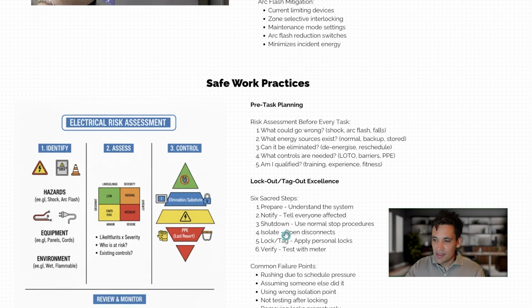Now, I mentioned this before, that lockout tagout is the principal way, when you have energy introduced into a system, that the people working on that system manage their own safety. It starts with pre-task planning, identifying what the work is, what systems they're going to be working on, what systems they're going to be working adjacent to, and how we isolate those. Typically on a project, you'll have an authorized isolation officer who's responsible for coordinating all of this. They work out where they are working and what they are going to be working near, they review the drawings, they plan the isolation, and they determine what systems are affected and where the isolation points are going to be.